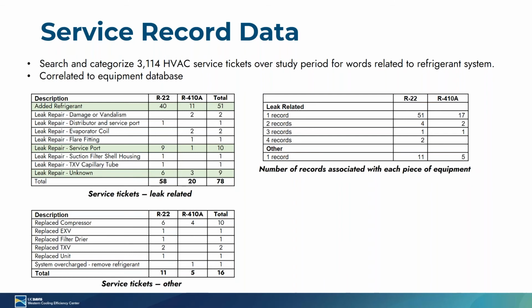We basically searched the service ticket database for words like Freon, R22, 410A, refrigerant, those types of words, and then we went ahead and calculated all this. What you can see is there's a couple of themes. We did notice a lot of cases where refrigerant was added, but there was no record of a leak repair being made. Essentially, just refrigerant added to replace lost refrigerant, but no identified leak or repair. We did see a lot of indications of service ports leaking, of Schrader valves leaking. And then the other most common repair is just a technician noting that they made a repair, but they didn't specify the location.